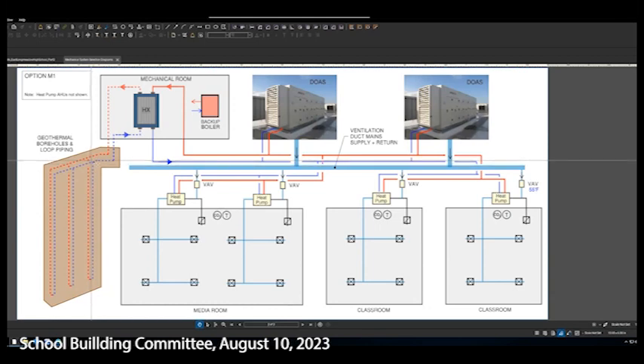And then all those vertical boreholes are tied together through horizontal piping that's brought into the building mechanical room. The fluid in that loop is pumped through a heat exchanger, so it's kept completely separate. There's another loop pumped through the other side of the heat exchanger, because we're purposely trying to isolate the geothermal side. The ground below the frost line is usually in the 50-degree range. So in the cooling season, we're rejecting heat to the ground, and in the heating season, we're absorbing heat from the ground.